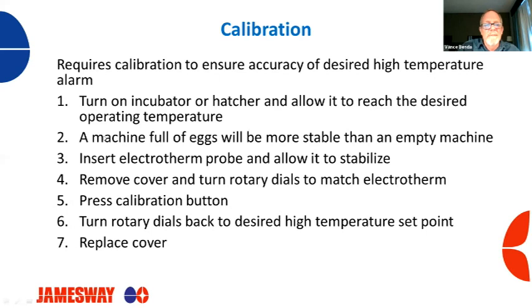Now, we're gonna talk about the electrotherm and probe. Like I said, you wanna make sure you get a good calibration, so it is critical that we calibrate the electrotherm. It's also critical that when we send it off to calibration, we send it with the probe that you're going to be using. And it's also critical, once you know this electrotherm and probe are calibrated, you keep these two together. You just don't want to mix probes up.